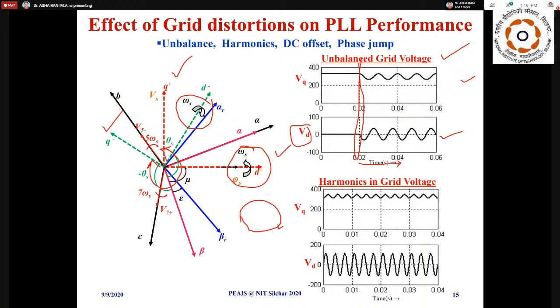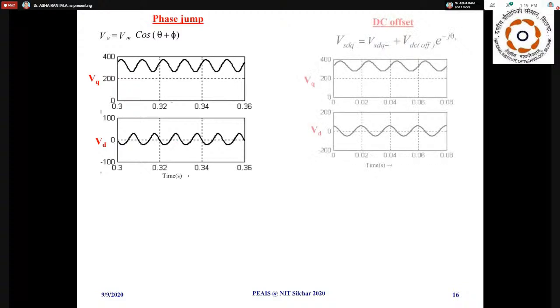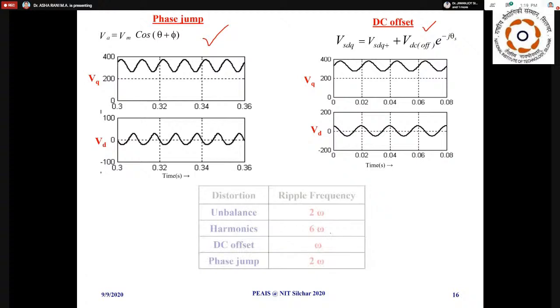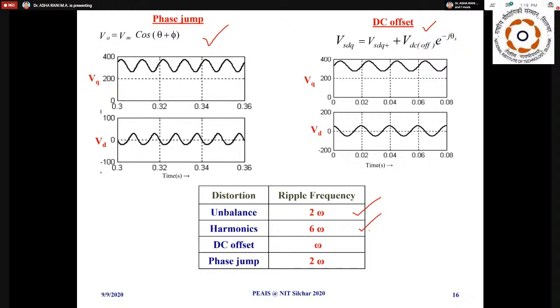Let us say I have fifth harmonic content; accordingly, you will have that frequency component inside. Then also your VD is not 0. Similarly, with other issues like phase jump or DC offset, your VD is also not 0. So this is the effect. When there is unbalance, harmonics, DC offset or phase jump, you will have additional frequency terms inside. As I told you, unbalance will produce a 2 omega term, phase jump will produce a 2 omega term, whereas DC offset produces an omega term and harmonics produce a 6 omega term.